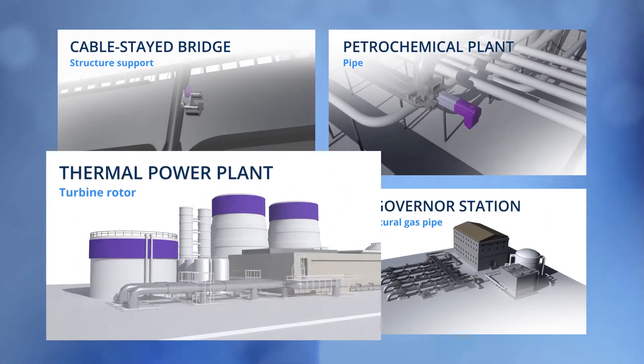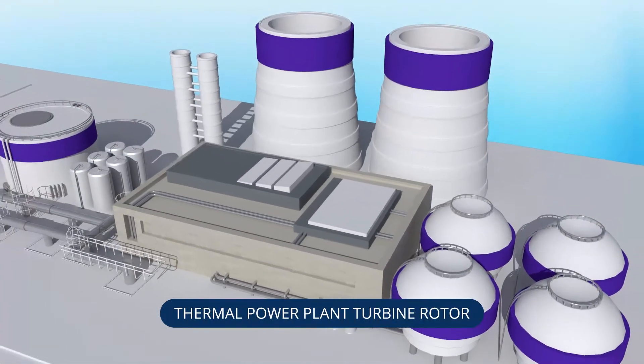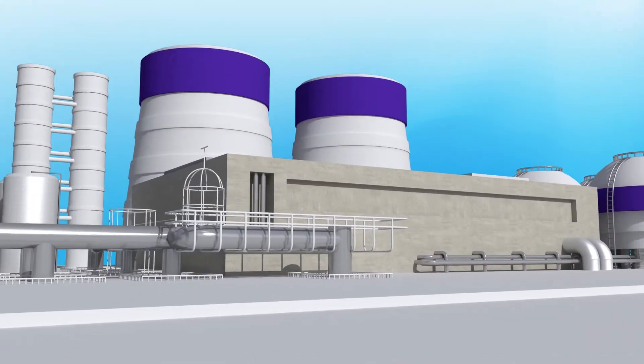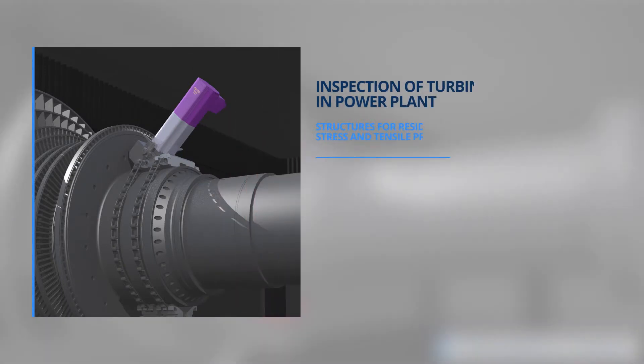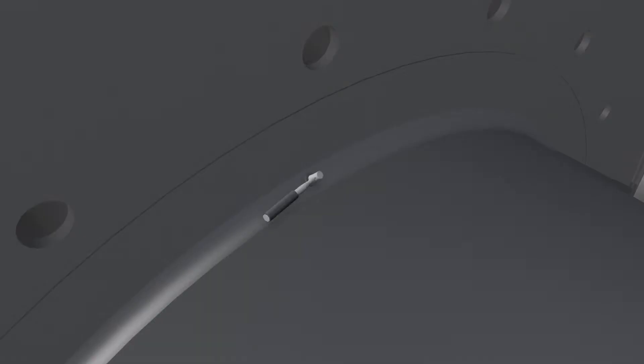The third case to be introduced is a thermal power plant turbine, and the attachment used is the Weight Light Chain System. The Weight Light Chain System is the attachment applicable to outer diameter 6 to 24 inch pipe and structure by adjusting the size with a light chain. The test object is a thermal power plant turbine rotor, and the test is intended to evaluate the remaining service life of turbine rotor parts. The size is applicable to shaft, casing, and valve.